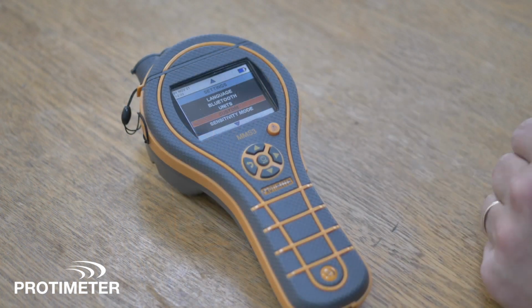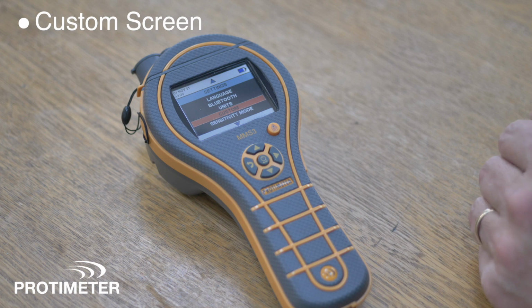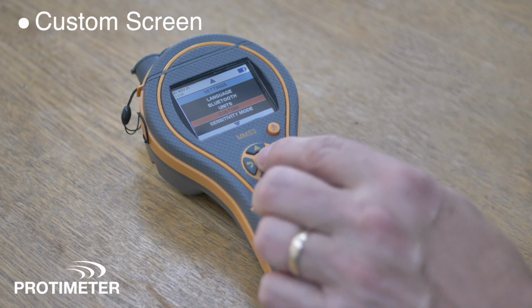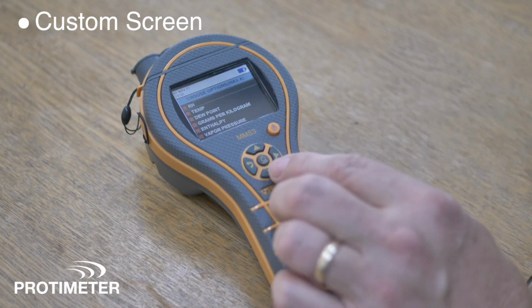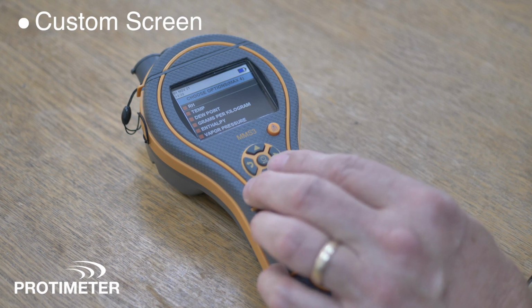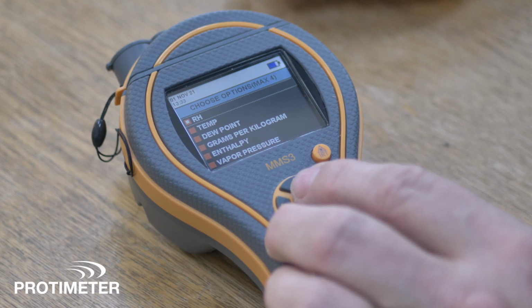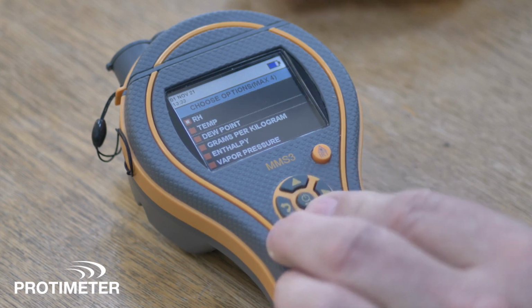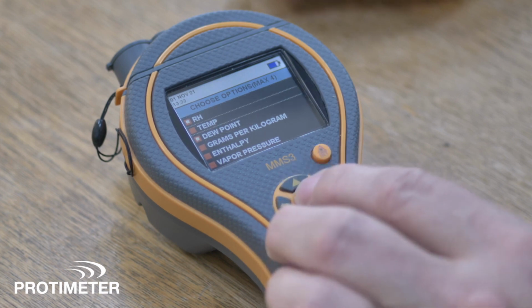We've also built into the MMS3 the ability to create a custom screen in psychrometric mode. In the settings menu we can go to custom, and select up to 4 different parameters. The readings will be shown in the order you select them. In this case we'll select relative humidity, dew point, temperature and vapor pressure.